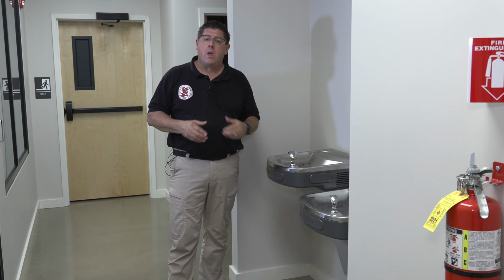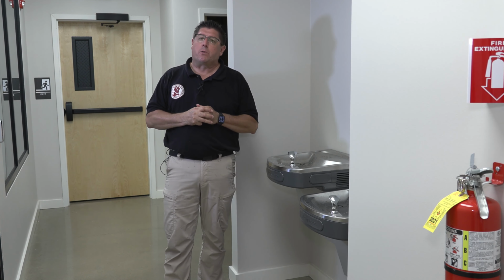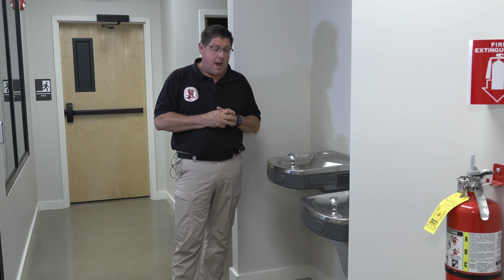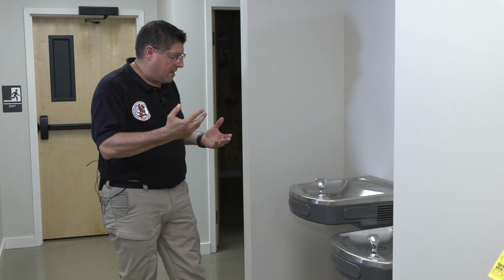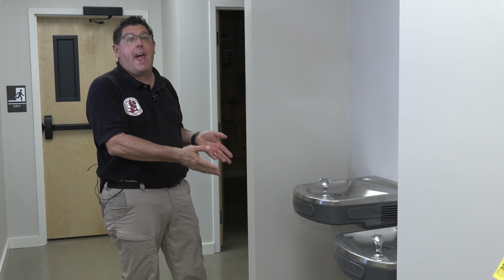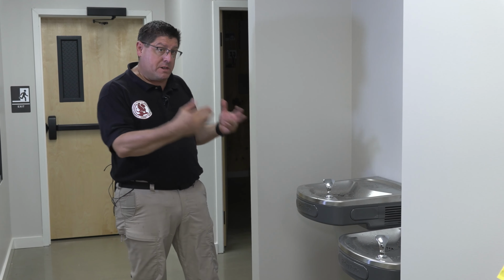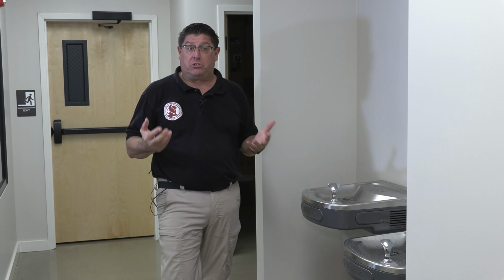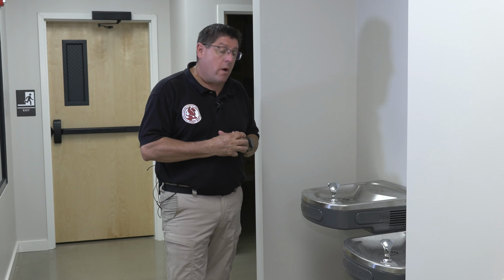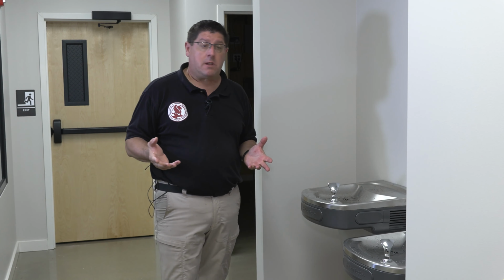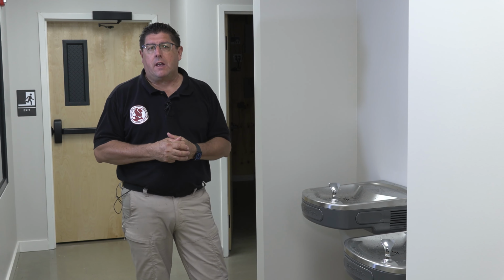There's our motor. One of the problems that we have with water fountains is if they're not used on a regular basis. I wouldn't necessarily be afraid of a water fountain that's located in a gymnasium where 100 athletes are using it an hour. But in a situation like this, where this water fountain could sit here for a day or 2 or 5 or 10 days between use, that water becomes stagnant, becomes stale, becomes bacteria latent. What we worry about is Legionella and Legionnaire's disease. And when that water comes out of it and it aerates, then that becomes something that can get somebody sick.